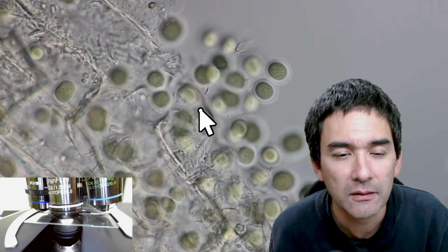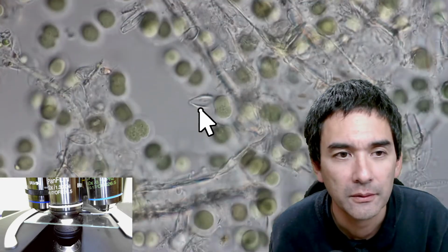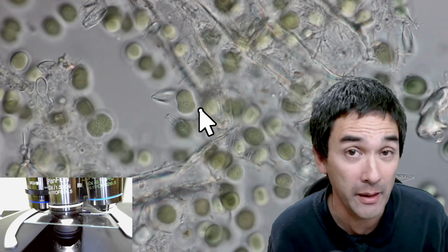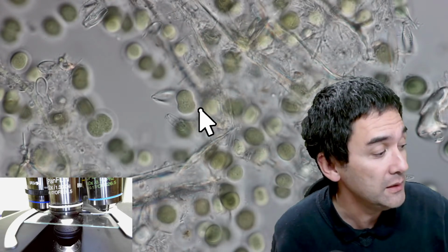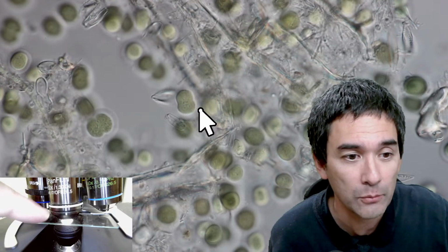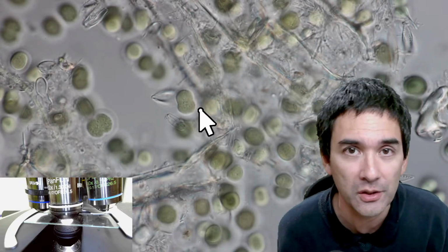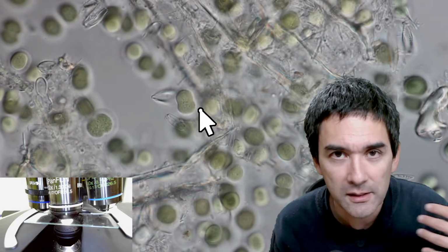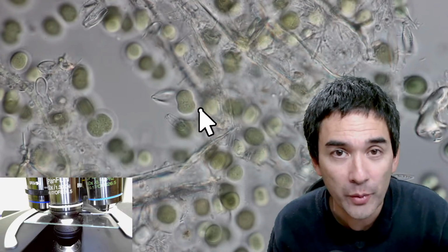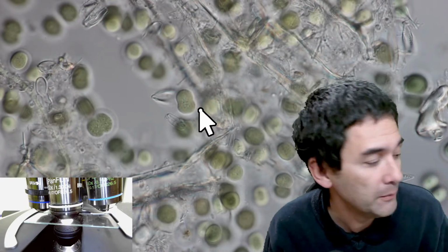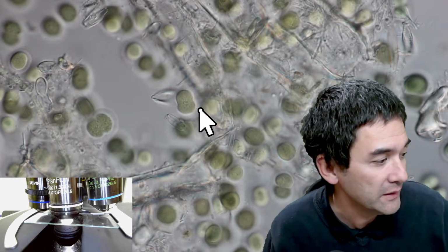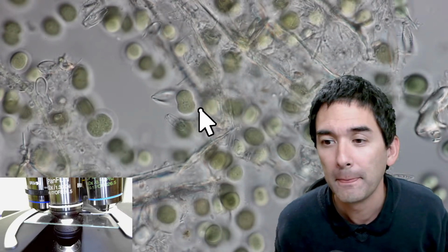So that is basically some diatom shells. But now what? If I go back now using the 60 times, I'm afraid of doing that, because I might indeed dip the 60 times objective into the immersion oil. I don't want to do that. So this is something where you have to be a little bit careful, because instinctively, like in my case, I like to switch magnifications quite often, and then you don't think, oh my gosh, I'm actually using oil immersion the whole time. You forget about that, and then you rotate it, and then it gets contaminated.